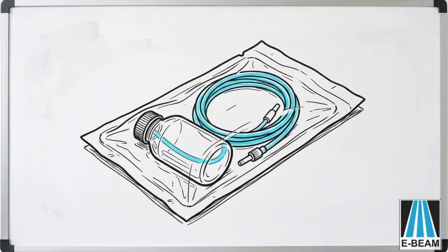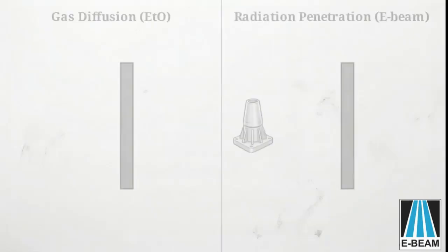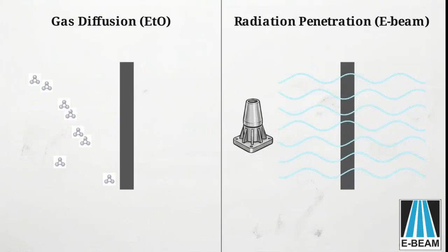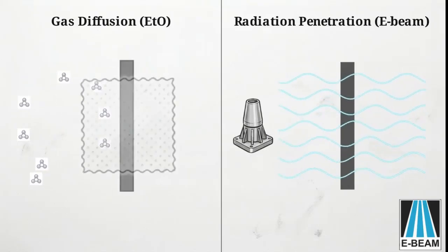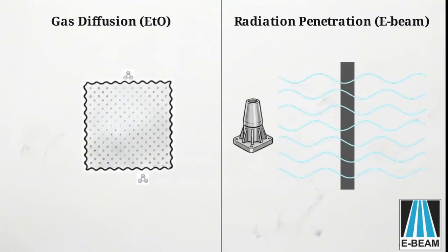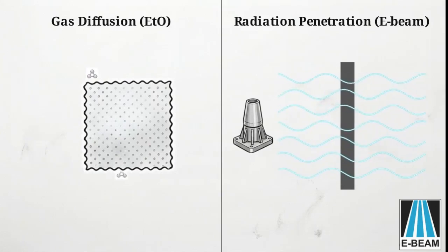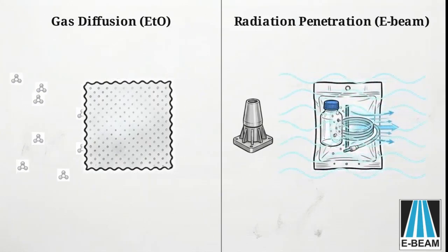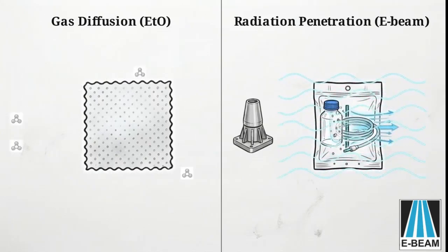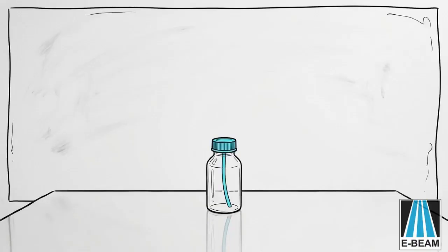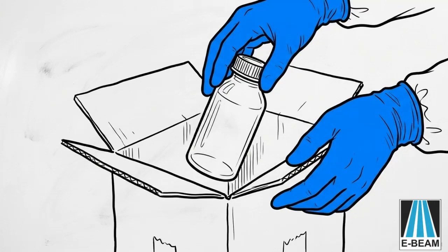Packaging became less constrained. EtO requires gas-permeable materials like Tyvek to let the sterilant in and out. ebeam doesn't rely on gas diffusion at all, so while Tyvek remains compatible, it's no longer required for sterilization performance. That opens the door to simpler, potentially more cost-effective packaging.